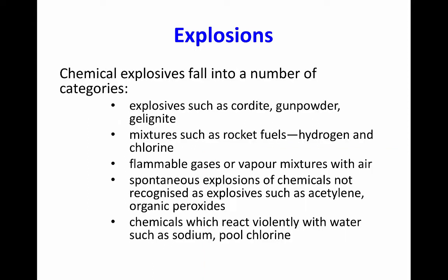Chemical explosions result when an unstable compound rapidly decomposes to form gaseous products. These gaseous products, if contained, result in a tremendous increase in pressure, which may burst the container. Some chemicals, such as acetylene, can undergo a double explosion. First, an explosion occurs inside the container, forming hydrogen and carbon particles. Second, the resultant build-up in pressure bursts the container, and the escaping products mix with air and may undergo a further explosion.